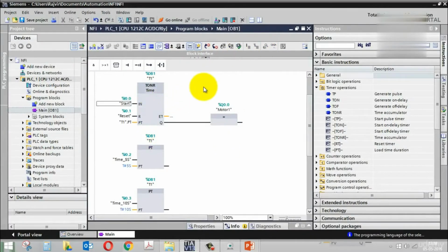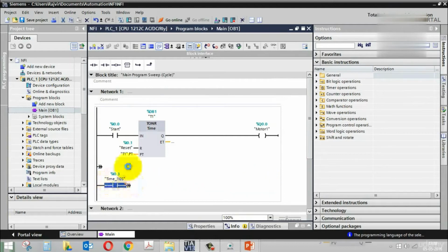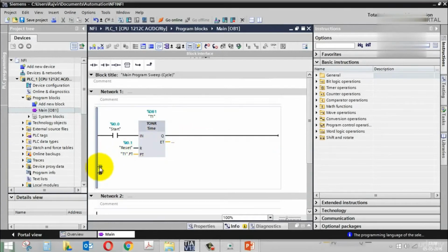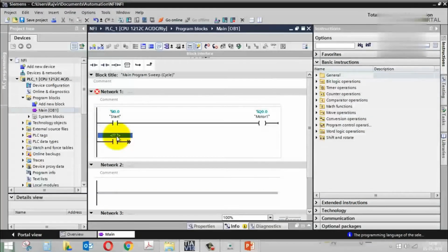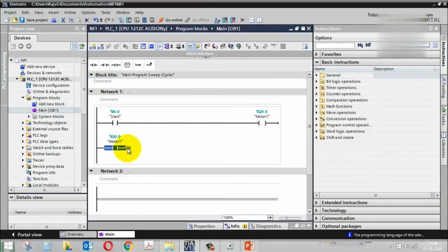This is the last logic. I'll go back to ladder and delete everything, because now we are designing counter logic. The first case was that we have to latch an output using I0.0. To latch the output, I'm going to use Q0.0 and use its contact in parallel for the latching. I'm not using set reset, I'm using simple latching logic. So you connect that here. Once I turn on my input, it will turn on my output and this will latch the output.